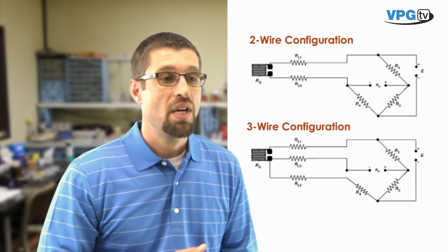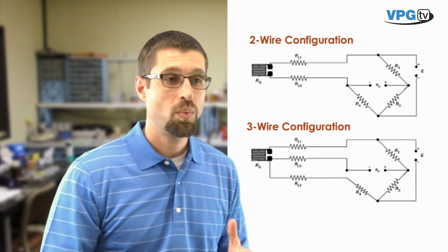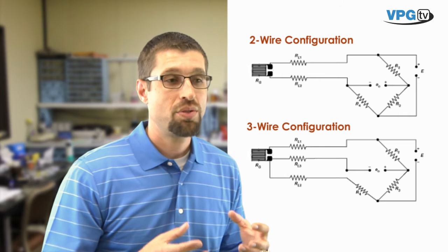The last thing is while both the two-wire and the three-wire setups will desensitize your reading a little bit, well they will desensitize your circuit, the two-wire actually desensitizes your circuit twice as much as the three-wire configuration.